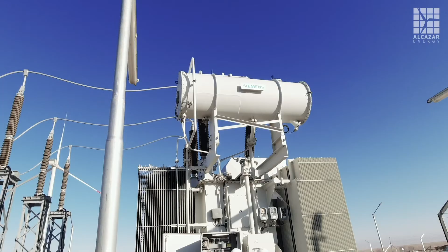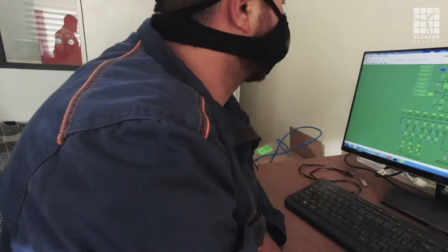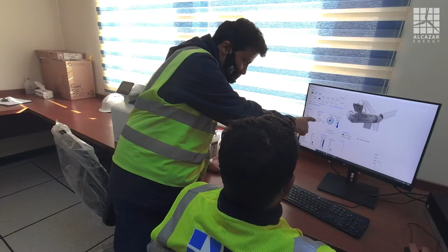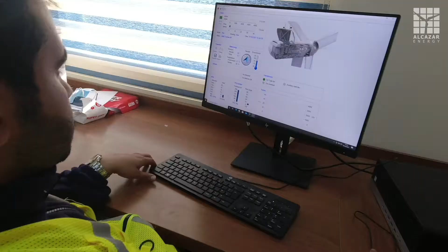Numerous tests are conducted after installation of all equipment, such as substation cold and hot testing, cables and SCADA testing, substation earthing system testing, and factory acceptance tests. Successful completion of these tests is required prior to operation to ensure correct functioning of the substation as well as the turbines. The Shobak wind farm achieved commercial operation in October 2020.